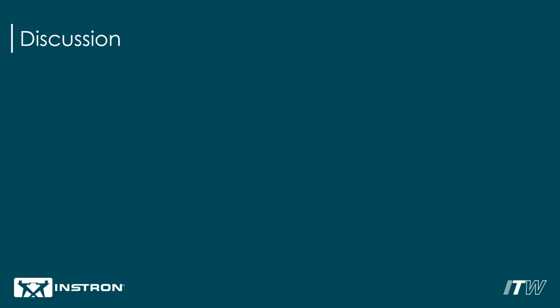Well, it's a work in progress, I would say. There is iDICs, which is the International DIC Society, and ASTM, and organizations in Germany as well, there's a lot of discussion about standardizing DIC at the moment. At the moment, there are no calibration standards that are directly applicable to DIC techniques, and developing them is quite involved because DIC just has so many degrees of freedom.